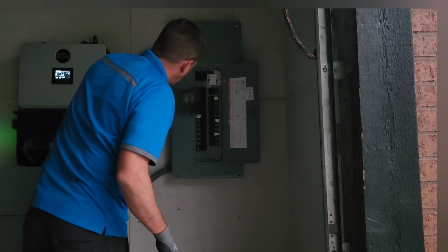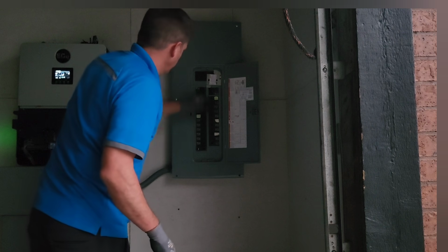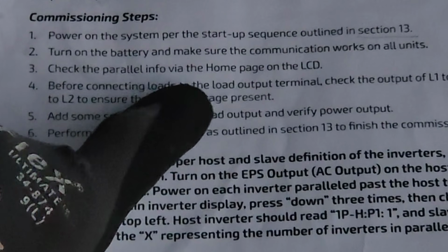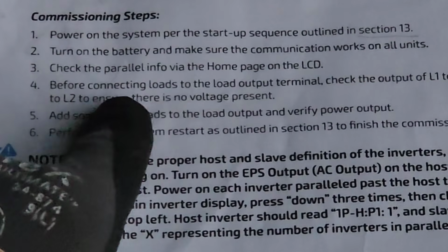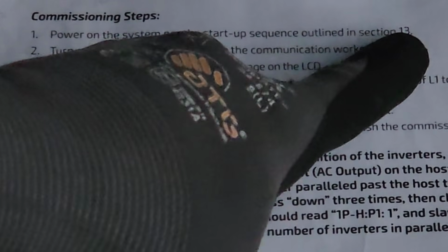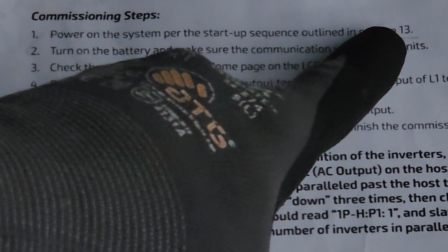I have all my breakers disconnected, off, except for my backfeeding breaker. Before connecting loads to the output terminal, check to ensure there is no voltage present. There should be voltage present though, since section 13 says turn everything on, so this step kind of conflicts with that. I believe I do have voltage, let me check it.